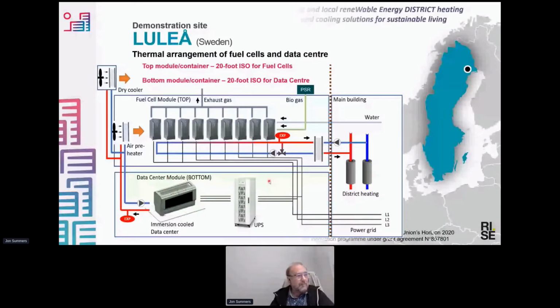We need to supply air to the fuel cells, coming from outside, and we heat it up using the liquid immersed solution in the bottom container. This is 22 kilowatts of IT immersed in a synthetic hydrocarbon, a dielectric, which circulates around the basin collecting all the heat. We use that to preheat the air to the fuel cells. The fuel cells then upgrade the heat further through a heat exchanger, into the return line from the district heating network in the adjacent building.